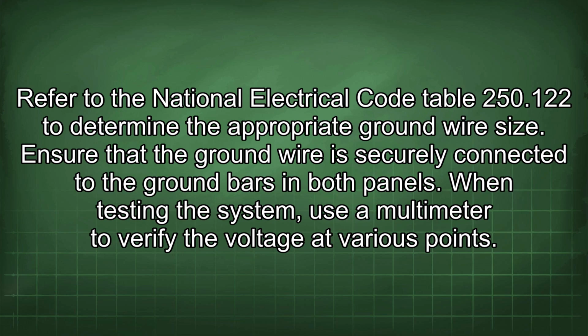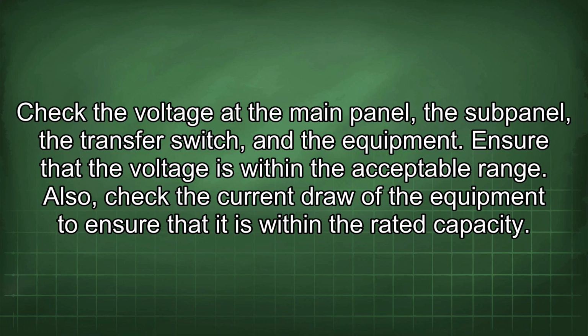When testing the system, use a multimeter to verify the voltage at various points. Check the voltage at the main panel, the subpanel, the transfer switch, and the equipment. Ensure that the voltage is within the acceptable range. Also, check the current draw of the equipment to ensure that it is within the rated capacity.